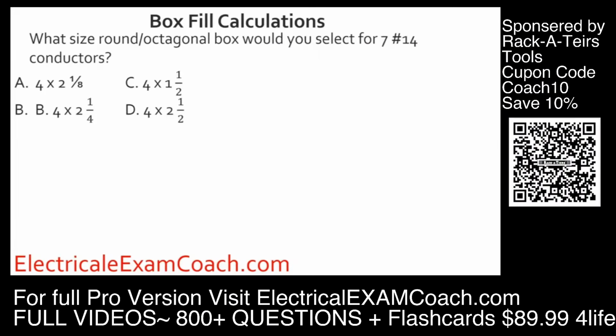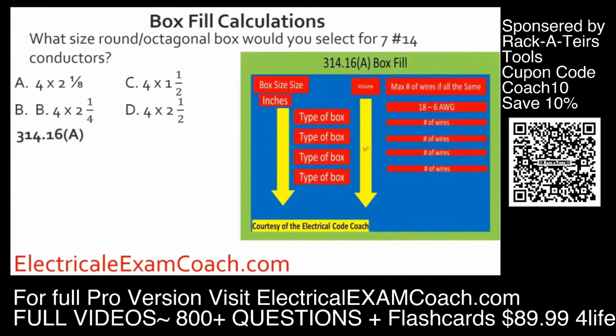What size round octagonal box would you select for 7 14 gauge conductors? We're going to head to table 314.16(A). We're going to start here on the right-hand side and find our gauge wire. Then we're going to come down and find a box that fits it, and be sure when we cross over that we stay in the right category of box, and we're going to select C.